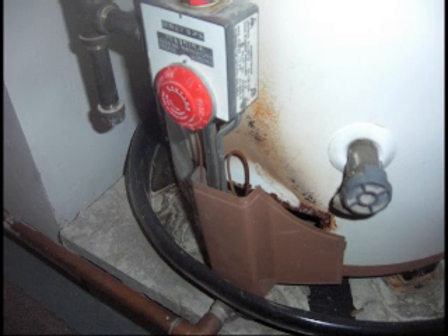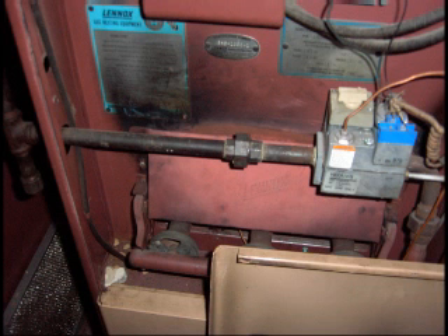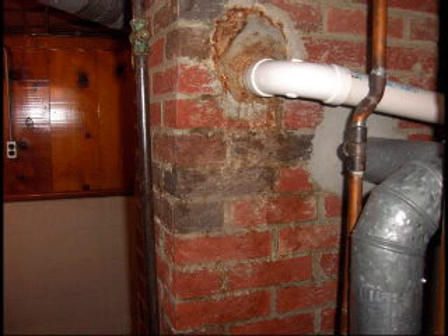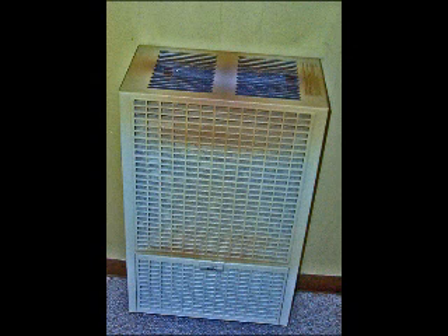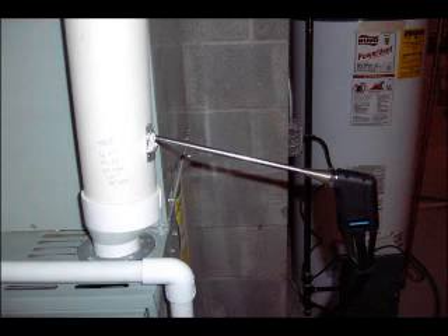One of the biggest scams is when they do find carbon monoxide, the heating contractors come out and they have no clue what's causing it. So then they're going to automatically say, oh, you have a cracked heat exchanger. You need a new furnace. And you know what? Many times you do have a cracked heat exchanger, but it was cracked because of these initial problems. It was never adjusted. So there was condensation inside the exchanger, and that's what caused the rust, and that's what caused the crack. If a contractor tells you that you have a cracked heat exchanger, you want to see it.